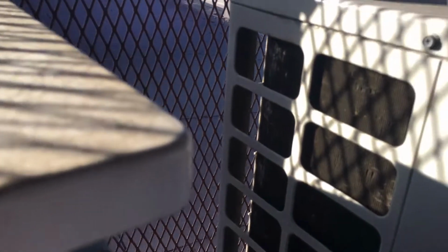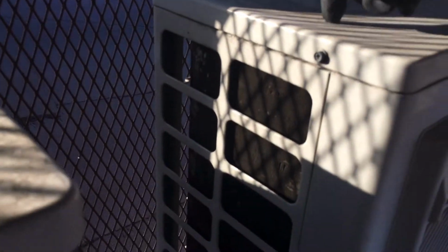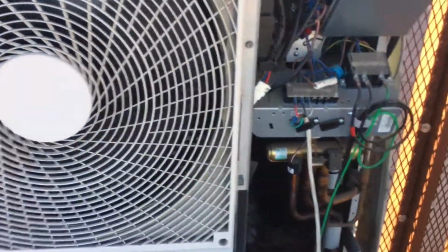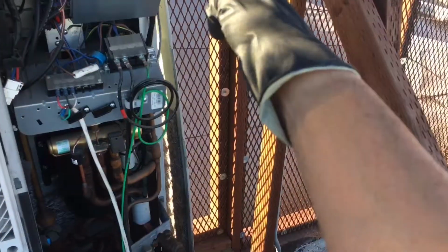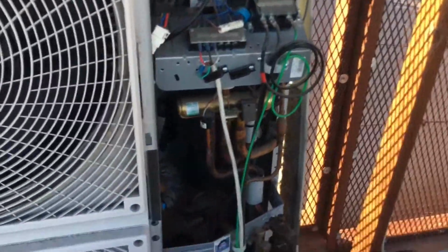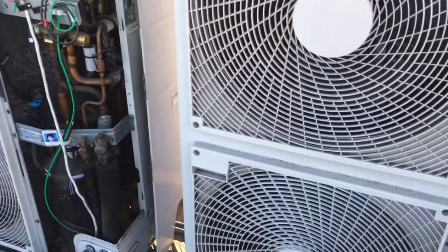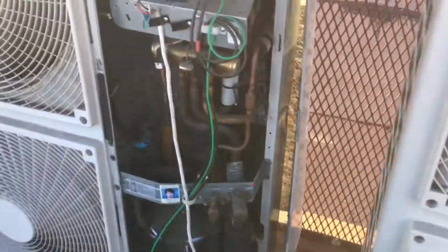It's actually, the solvents are pretty corrosive on aluminum as they get on. They're starting to eat the condensers that are closest to that outlet of that duct right here, have more decay and are starting to corrode, compared to the one at the end which is cleaner and has no corrosion. So basically the body shop next door is destroying this customer's AC units over time, which this will probably be the first one that springs a leak and corrodes away, because it's within like 10 feet of the outlet of a spray duct that has solvents all the time coming out of it. And other than that, this was an easy clean install.